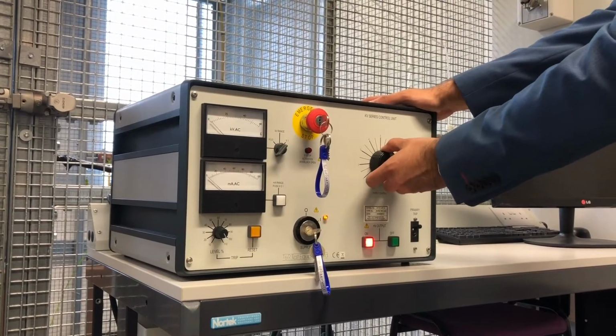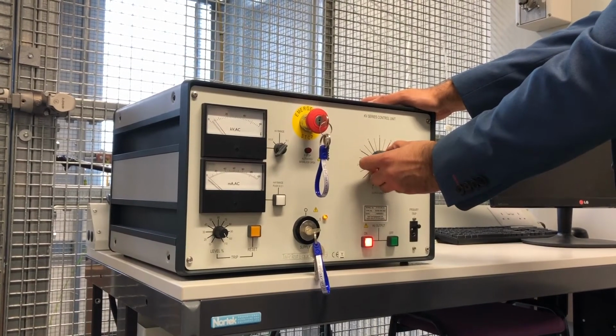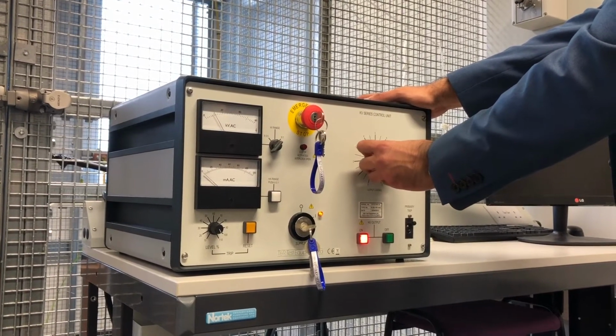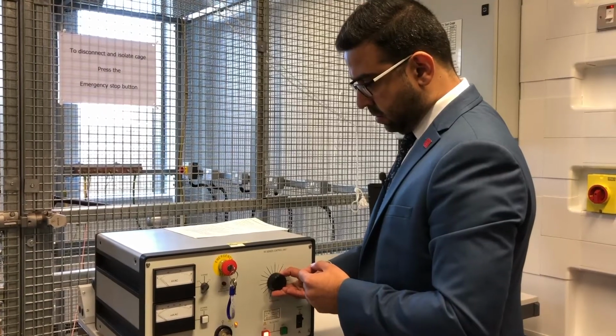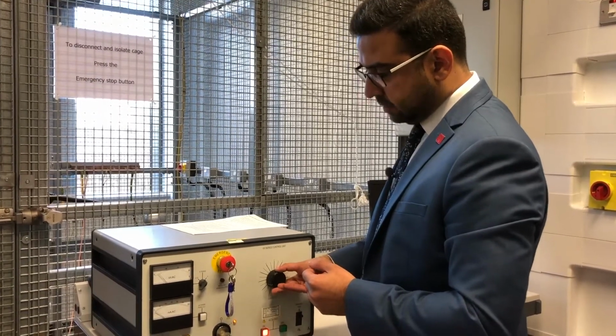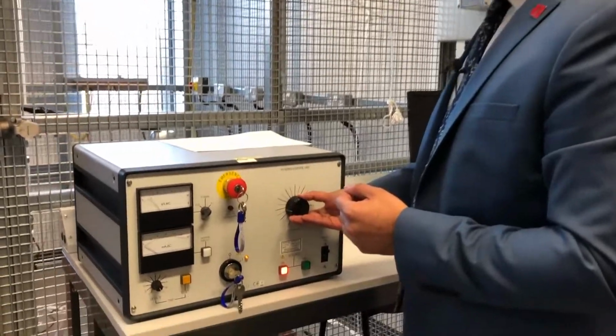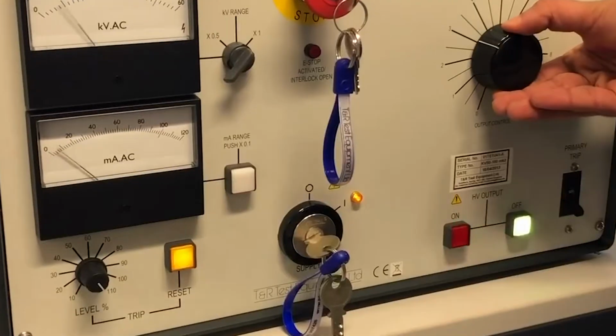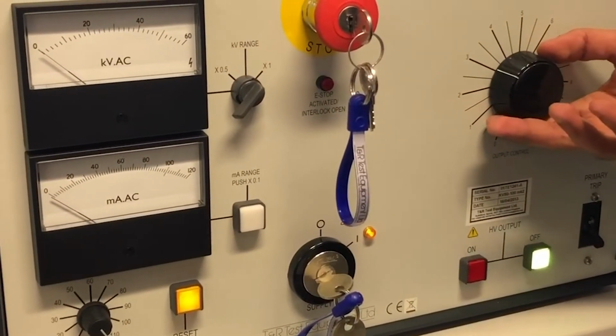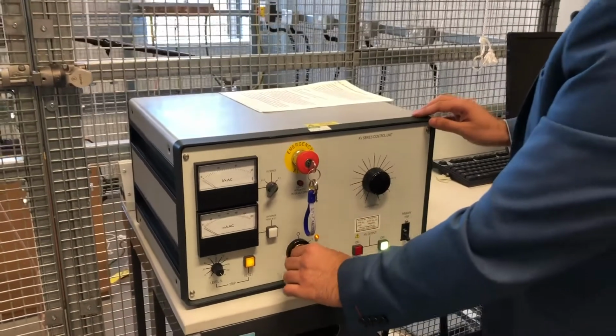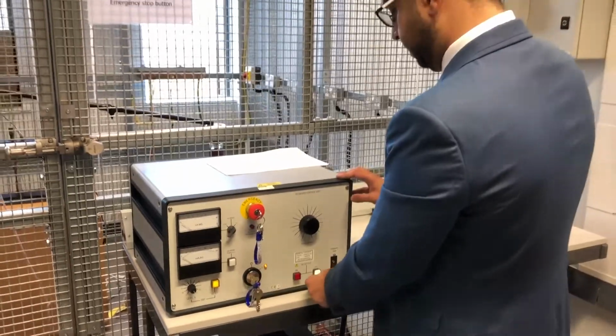System is ready. We could start increasing the voltage and you'll be able to see the actual air breakdown. We're at 5,000 volts, 10,000, 20,000, and the circuit breaker has tripped. Safely switching the system off.